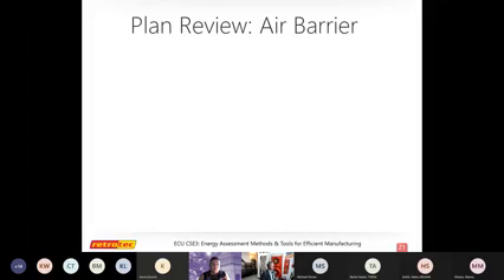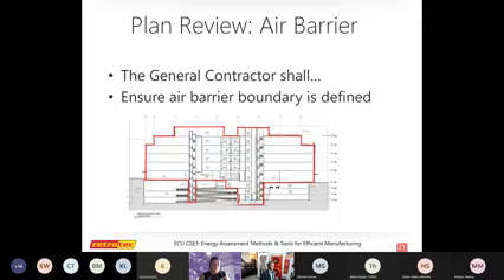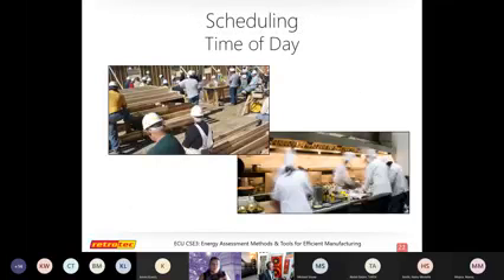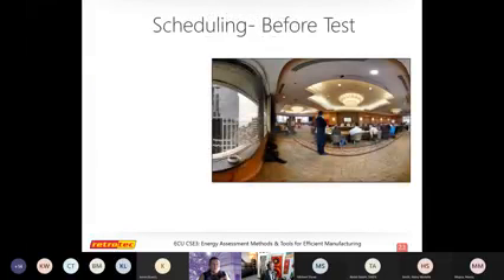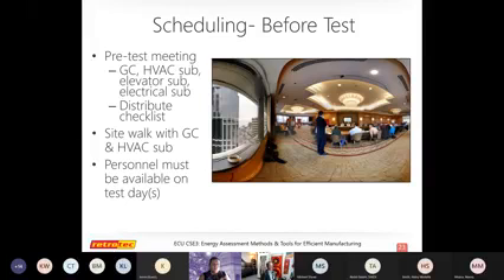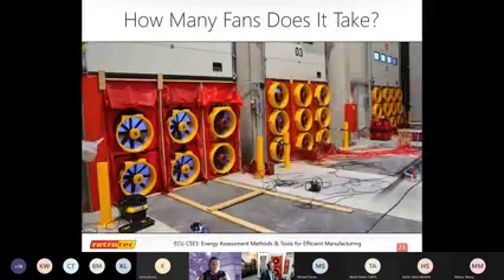So if you're ever wanting to look into getting a test done, I talked about the air barrier and planning that out. The time of day is nice, especially if it's a current plant that's under operation. A lot of the time they'll come in and do the test at night after everybody has gone home for the day. Sometimes you can get nicer thermal images at night as well. The fewer people that are in there running around, the easier the test will go. And then just having everybody involved, from the building owner. If you have a building engineer, it helps to have that person there. And the HVAC contractor, just to see the building automation software, somebody who's knowledgeable to run that, to make sure the mechanicals are off when the test is run and all that. So just some things to look out for.